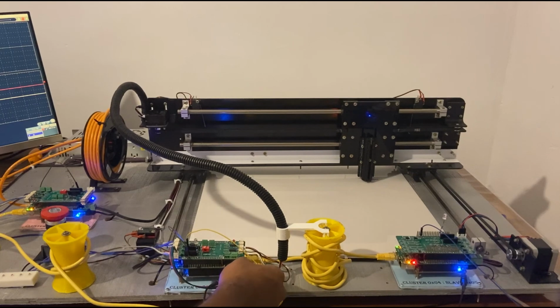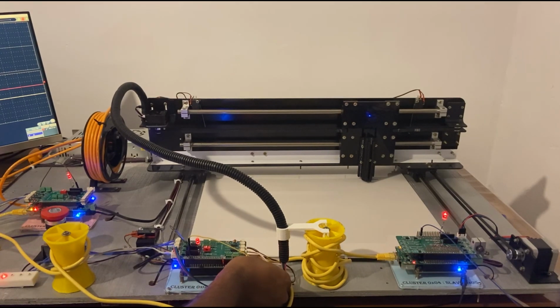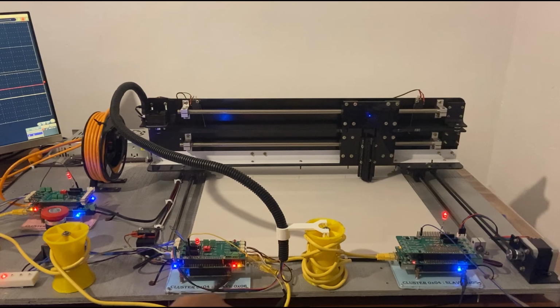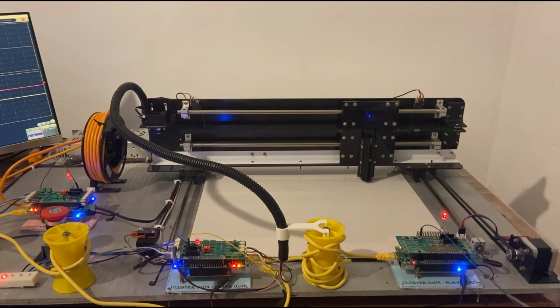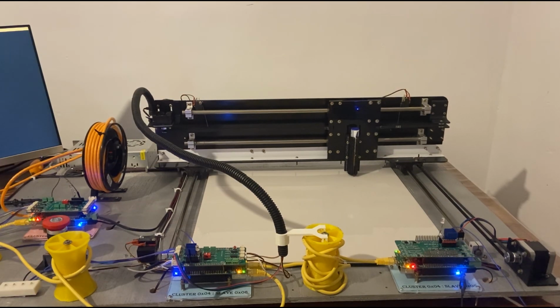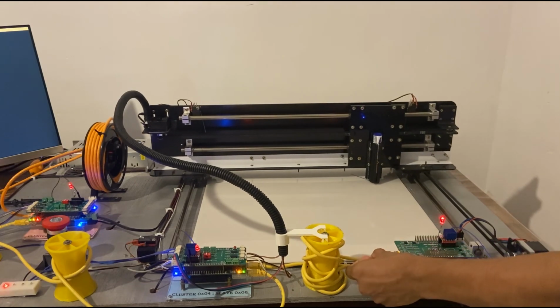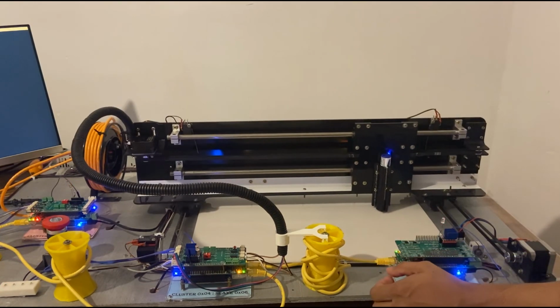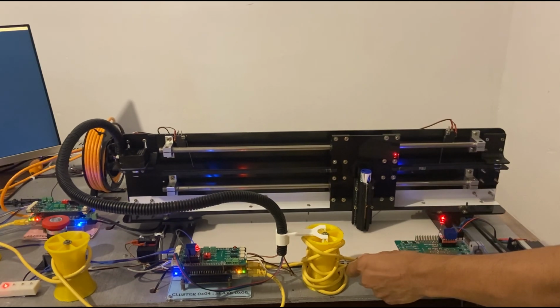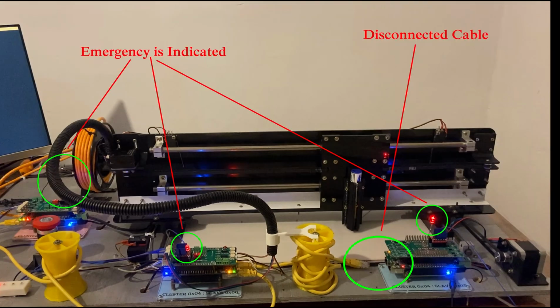To demonstrate this first, we are going to disconnect the link between slave 1 and 6. You can see the slaves are going to emergency enable state. Here slaves 6 and 5 will call their emergency locally, while slave 1 will receive emergency from master. Next, we are going to disconnect the link between slave 6 and 5. Here also slave 5 will call its emergency locally, while slave 1 and 6 receive the emergency from master.